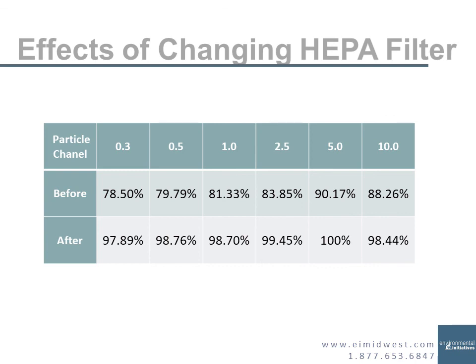Now I know what some of you are thinking. You're thinking, well, Cassidy, once my filter gets full of dust, won't that dust collect more dust and make it harder for particles to go through? We said that was an effect that happens, and then you see the pressure drop. Yeah, that's true. But at some point your filter is overly filled with particles, and particles are just going to be pushed back off of the filter. So make sure that you regularly change your pre-filter and occasionally change your HEPA filter.